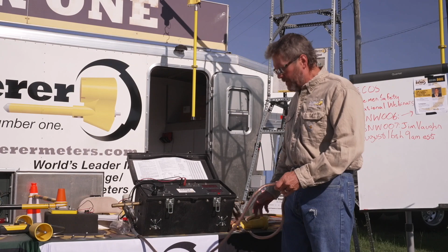You also want to complete a mechanical inspection, which is when you grab hold of those clamps and verify there are no loose components. You literally grab the clamps and try not to twist the clamp off the ferrule. Make sure the cable is tight in the crimps, nice and tight. As long as it looks good and passes the mechanical inspection, typically these TPGs do well in electrical test.